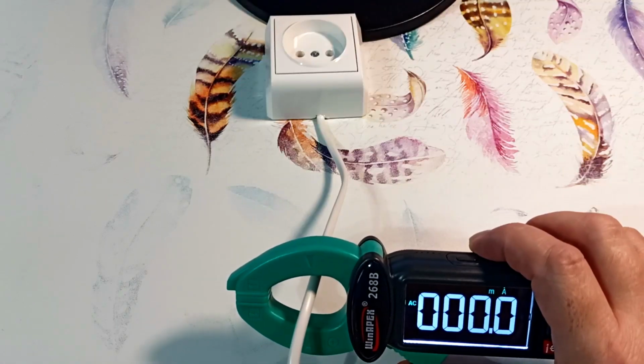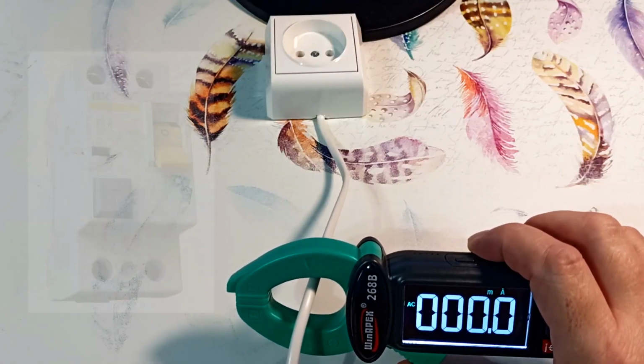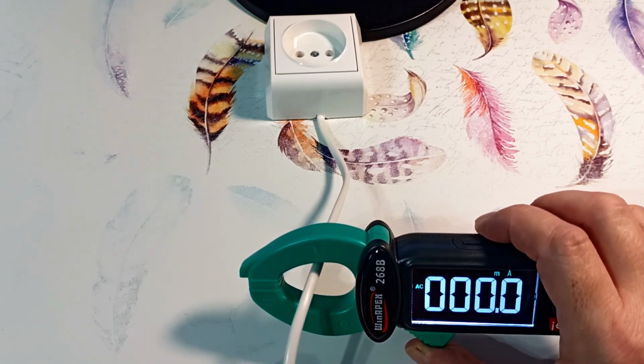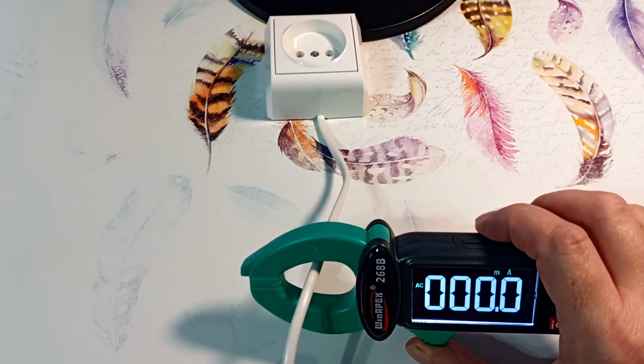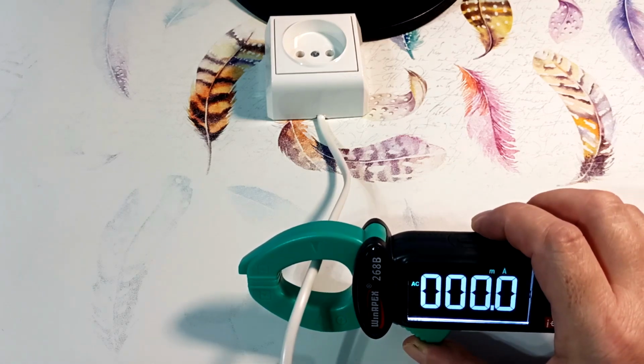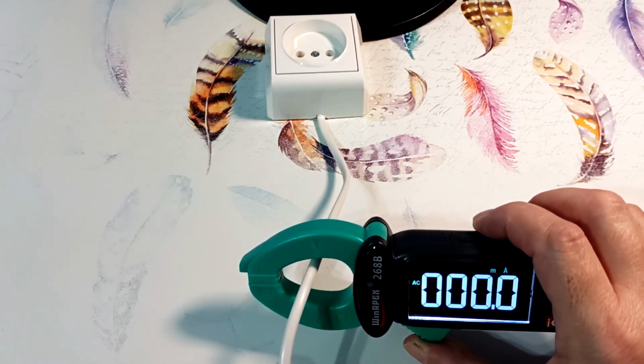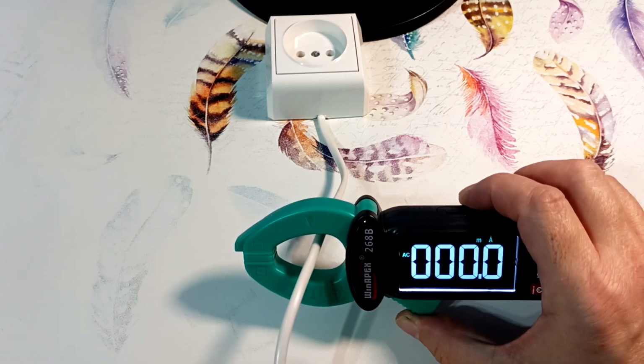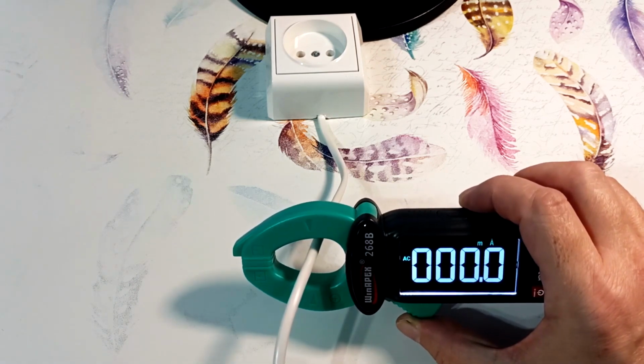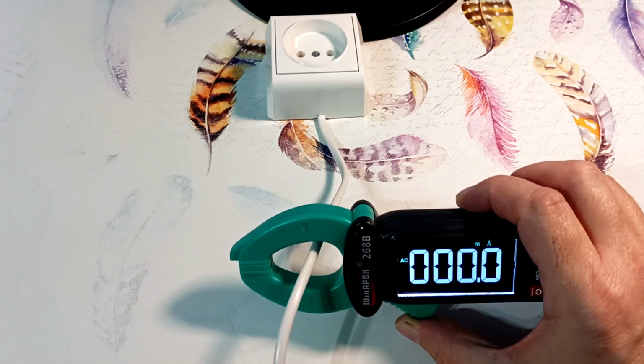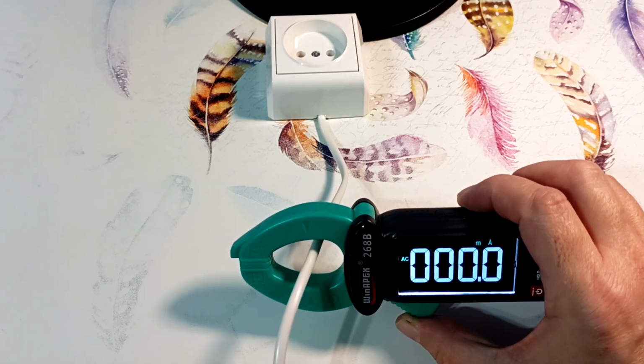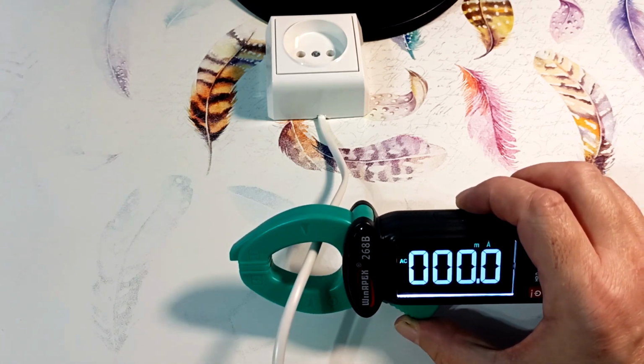The measurement principle is the same as in an RCD, in a residual current device. We simultaneously enclose both wires in pliers, the neutral and the phase. If currents of different values flow through them, the device will show the difference in the values of these currents. That is, a leak occurs in the load, the value of which was measured by the device.